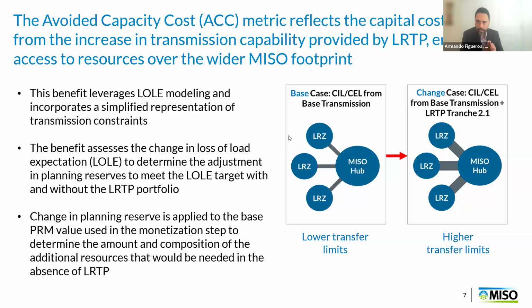We start with a case that doesn't have the effects of the portfolio - a case that includes transmission transfer constraints, but without the transmission portfolio we're evaluating. We run a simulation and drive the system to criteria. Then we add the portfolio and reliability increases, because you have more capacity in those pipes to share resources during various types of needs, not only during the critical periods normally analyzed in power flow. We look at 8760 hours, different weather years, and different samples from an outage and generation outage point of view.